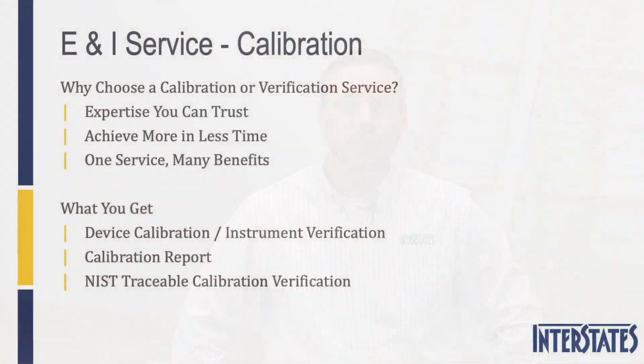Some of the common services I see out there are instrumentation calibrations, where each device is pumped up or heated up, or flow is run through a device on a periodic basis, and the results from that calibration are documented in a sheet and turned over to the facility in the end. That way the facility has a means to know that this device was calibrated on this date, it was working properly, it was accurate, or maybe on the other hand, this device needed replacement, its electronics were fried, its calibration was off and unable to be adjusted. That's one of the E&I services that's out there.